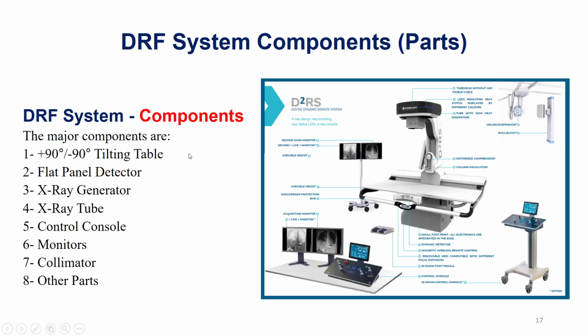Now we'll start our talk about the flat panel DRF system, which will be used as a model of the medical devices and systems in hospital for the application of the new purchasing tool. So what are the major components or parts of the system? The major components of the DRF system are a tilting table with a plus 90 degree tilting angle and a minus 90 degree tilting angle, a dynamic flat panel detector, an X-ray generator, an X-ray tube, an operator's control console, monitors, X-ray field collimators, as well as other parts.